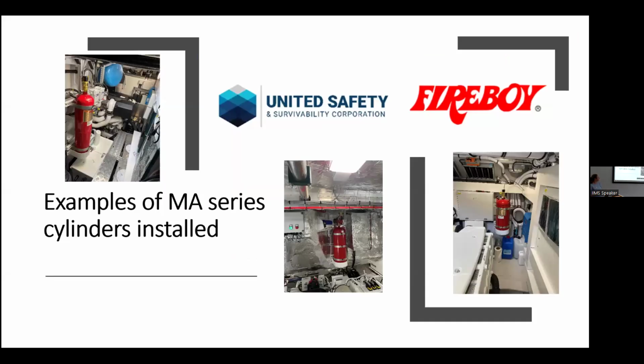This is samples of some of the installations on some of the boats. As I mentioned before, the position is very important. Ideally, you want the extinguisher fitted on a center line. That's not always going to be possible. So deviation in a clear space somewhere where you've got an open space for the 180 nozzle to reach all of the space.